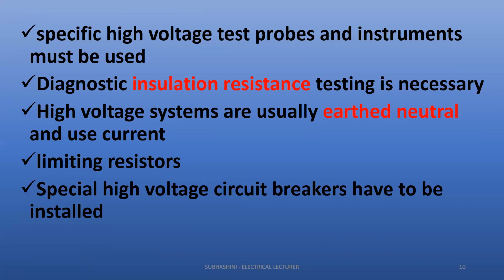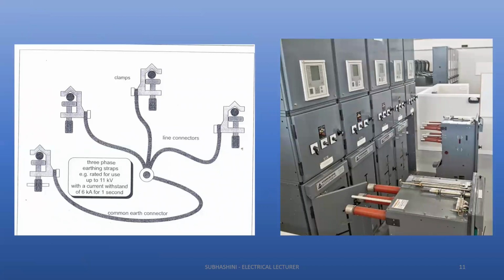High voltage systems are usually earth neutral and use current limiting resistors. Special high voltage circuit breakers have to be installed. So this image is what I'm shown. All our clamps are connected together and earthed in a common earth connector for up to 11 kV. This side is the automatic operation of the switching devices, that is, the switching strategy, how the switching systems are done.